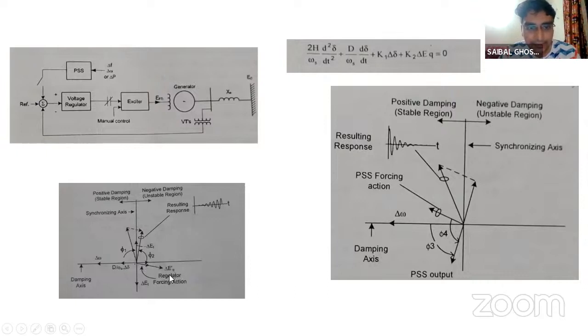So this regulator action can bring this resultant, which was previously in the positive damping side and positive synchronizing side, into the negative damping side due to this very high response excitation system. So you can see that this resulting torque is becoming unstable.